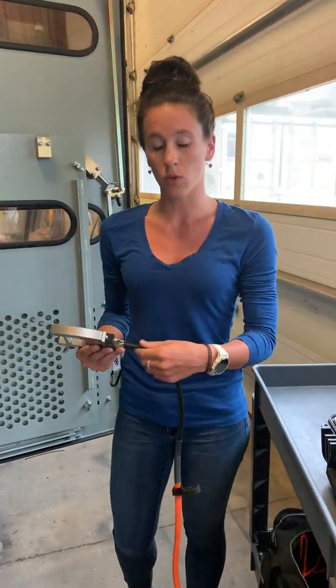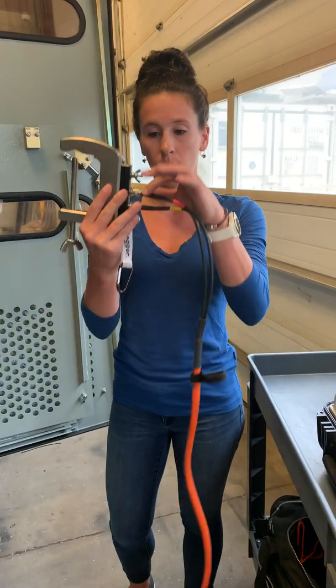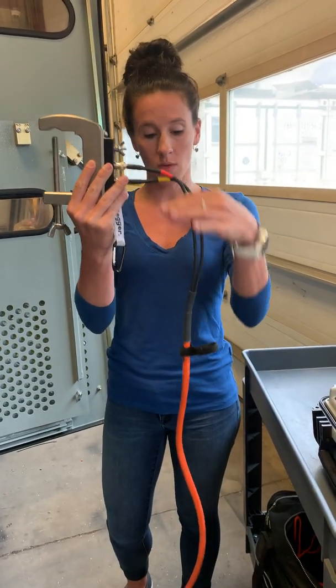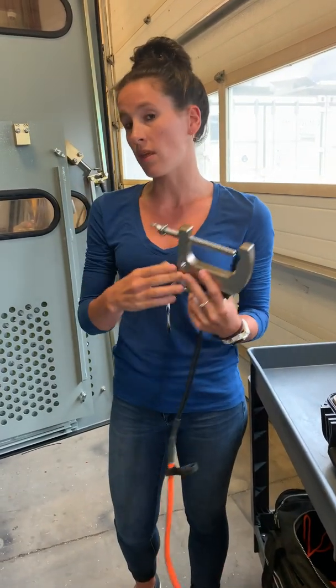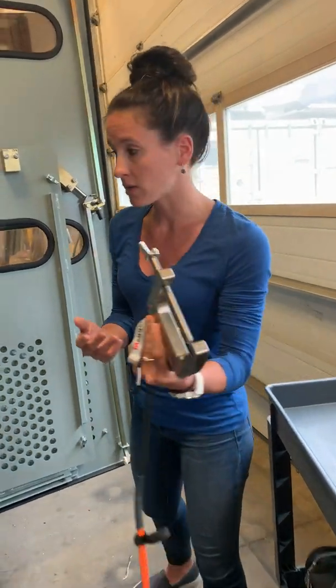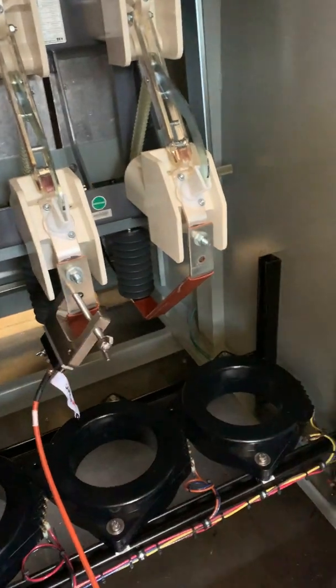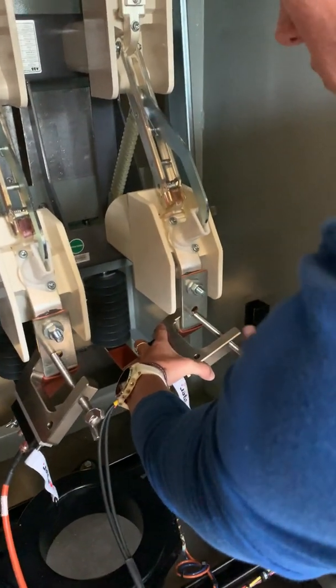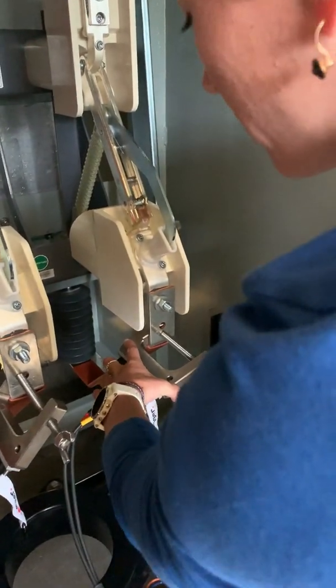Take the other side of each orange lead. It doesn't matter which one. Plug the orange and the yellow, they're together, into the one clamp, and then the black into the second clamp. And then you're going to take your clamp to the bus bar, wherever your connection's going to be. Here I'm doing a face-to-face connection. And just twist it right on there.